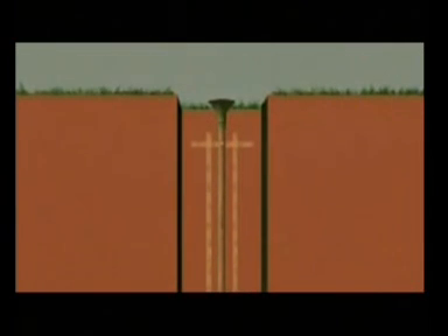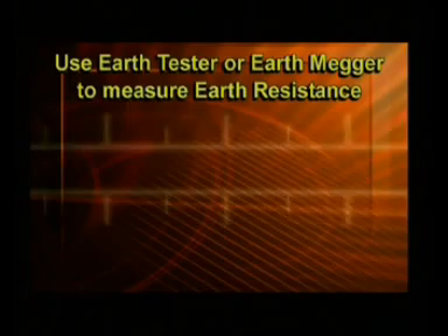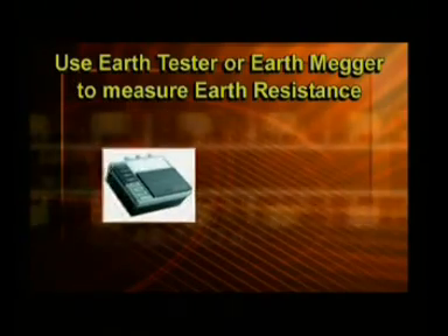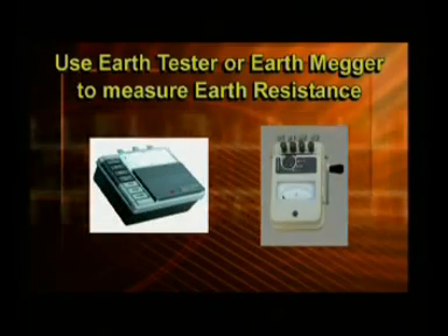On the top of the earth plate, a funnel made of mesh is affixed. The entire pit up to this funnel is then filled with red or black soil or with murum. This helps to retain the moisture in the soil. Next, for safety purposes, a chamber is prepared below the ground level around this mesh funnel and it is covered with a GI plate. To measure the resistance of the earth, an earth tester or earth megger is used.